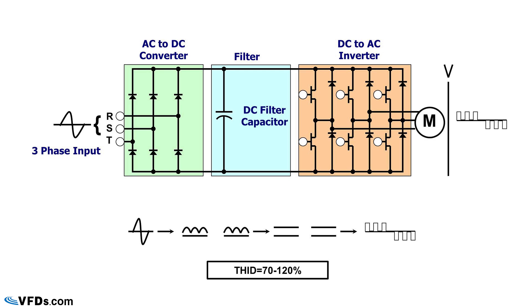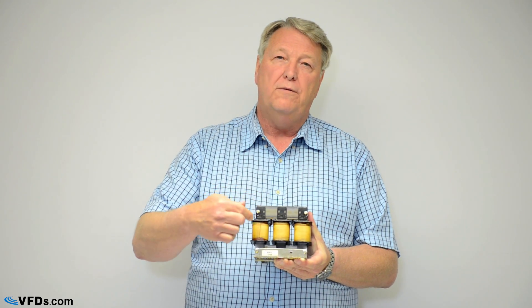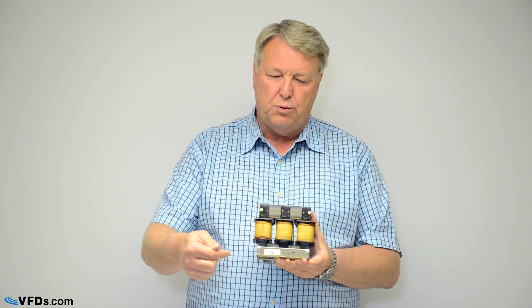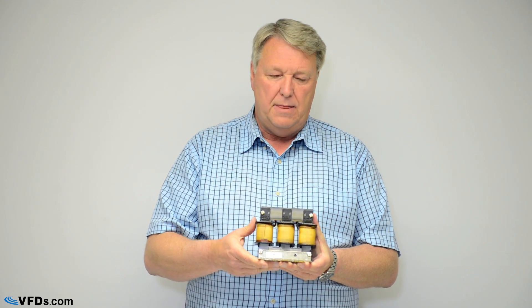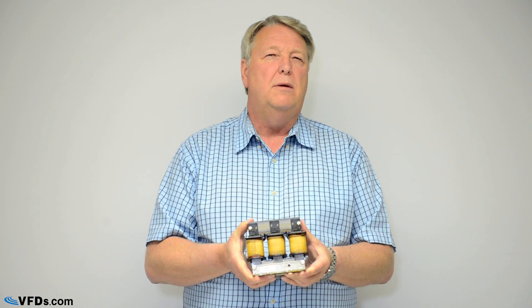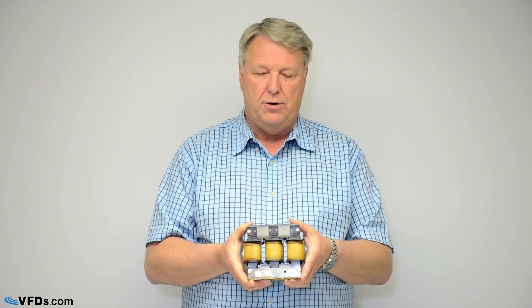It can even create legal liabilities when these harmonics cause problems. Now the first, cheapest, best way of reducing these harmonics is with a three-phase line reactor. I'm holding a three-phase line reactor in my hand here. We call this a reactor, even though it's actually composed of three reactors — one for phase A, one for phase B, one for phase C. It's a very simple item to install. You bring your three phases into there, and then you bring three more lines out and go to your variable frequency drive. This device will eliminate two-thirds of the harmful harmonics that exist in your power distribution system.